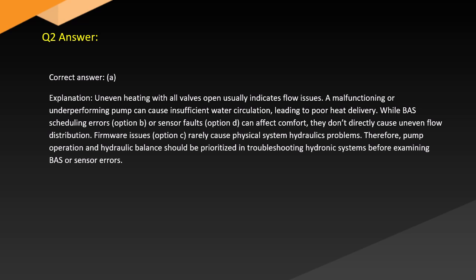Firmware issues, option C, rarely cause physical system hydraulics problems. Therefore, pump operation and hydraulic balance should be prioritized in troubleshooting hydronic systems before examining BAS or sensor errors.